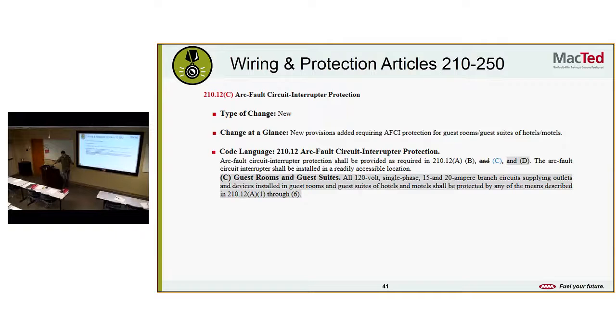But according to the code, they've added new provisions requiring AFCI protection for guest rooms, guest suites of hotels and motels. All 120 volt single phase 15 and 20 amp branch circuits supplying outlets and devices installed in guest rooms and guest suites of hotels and motels shall be protected by any of the means described in 210.12. Everything needs to be an arc fault. They don't want people dying in hotel rooms.